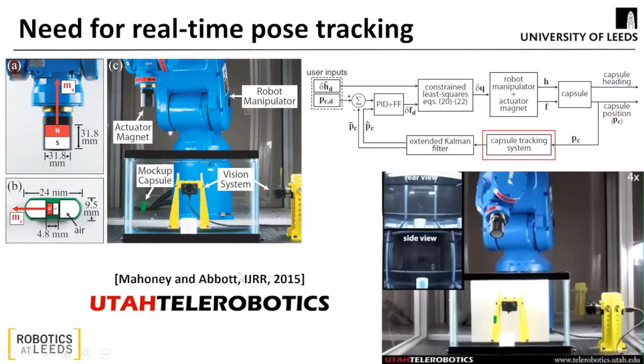To apply a similar approach to patients, we need a pose tracking strategy that is able to localize the device inside the human body and that is not affected by the magnetic field used for actuation. This excludes all solutions based on electromagnetic tracking, as coiled sensors used there are subjected to saturation when exposed to the high magnetic fields. So we developed our own real-time pose detection strategy by integrating 1 accelerometer and 3 couples of Hall-effect sensors inside the tip of the magnetic endoscope.